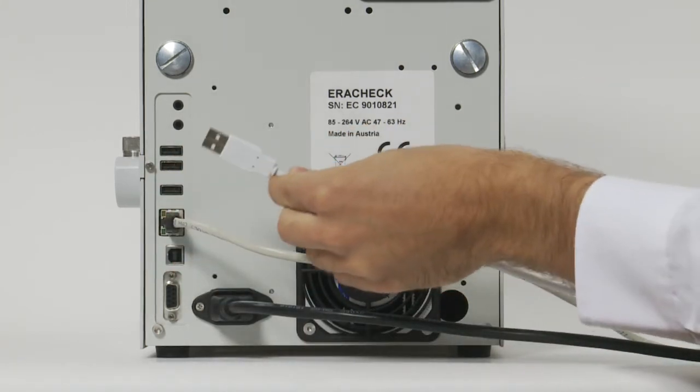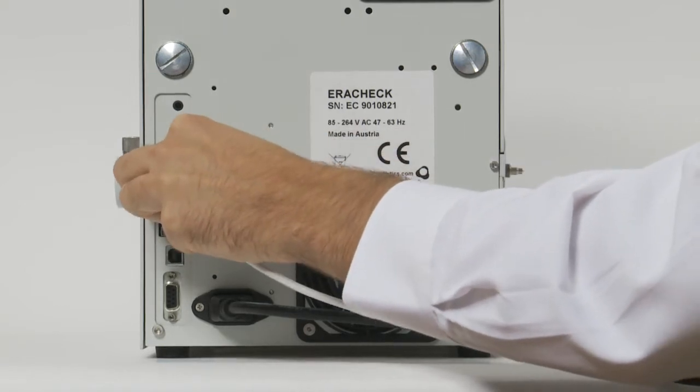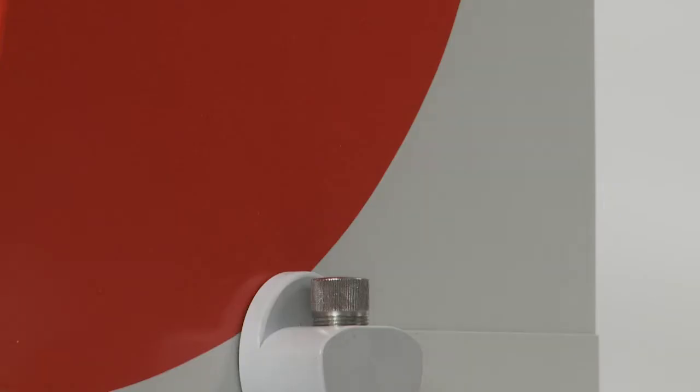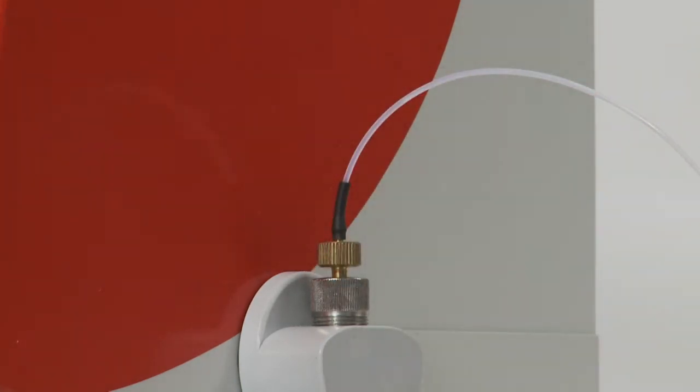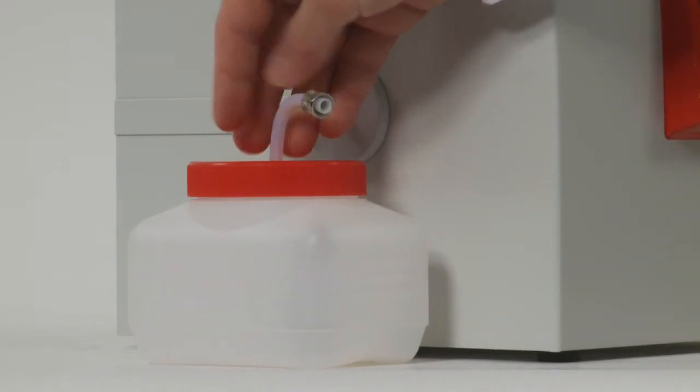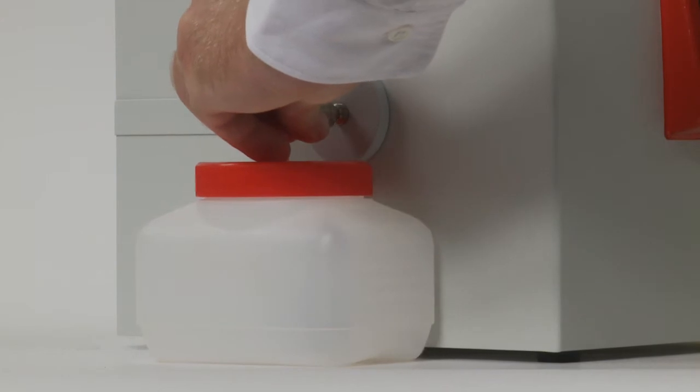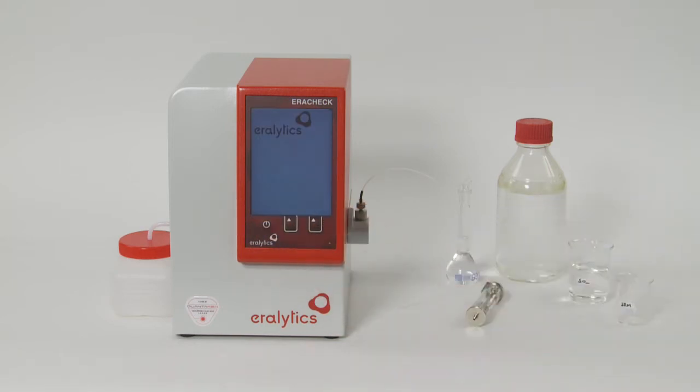Put the inlet tube in the luer inlets on the right side of the instrument. Then place the waste container next to the instrument and connect the outlet tube to the outlet on the left side of the instrument. Switch on the analyzer by pushing the power button on the front.